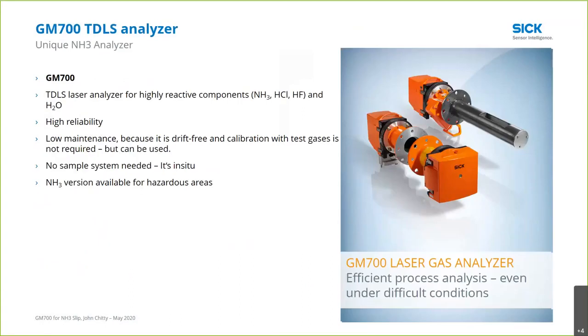So now to take a look at the GM700 technology. It's a tunable diode laser spectrometer. It's a laser analyzer for highly reactive components such as ammonia, HCl, and HF. Pick any one. We can't do all 3 at the same time. However, we can measure ammonia and water at the same time. It's very, very reliable. It's very low maintenance. It's drift-free, has no moving parts, and it can be calibrated without a test gas.